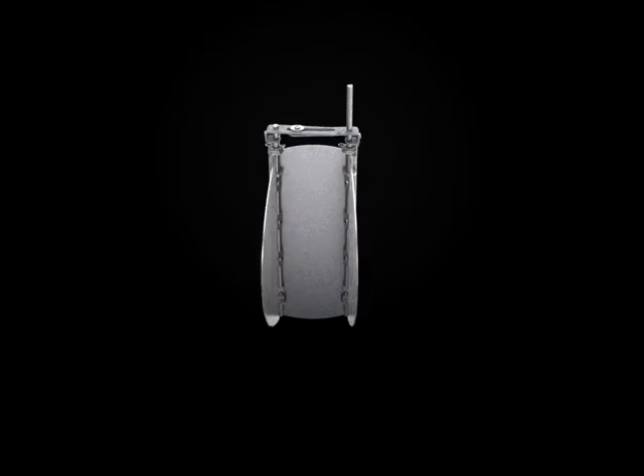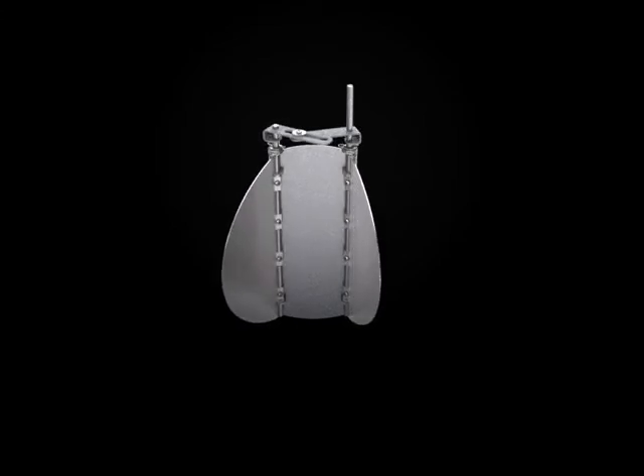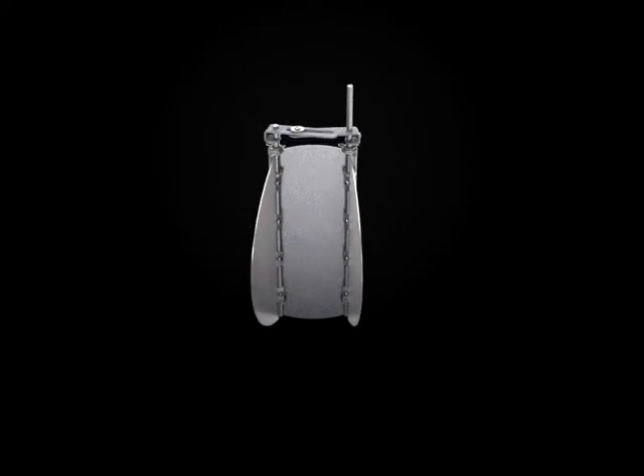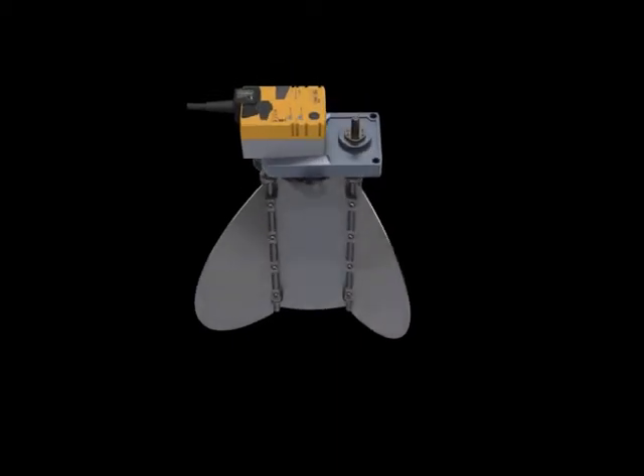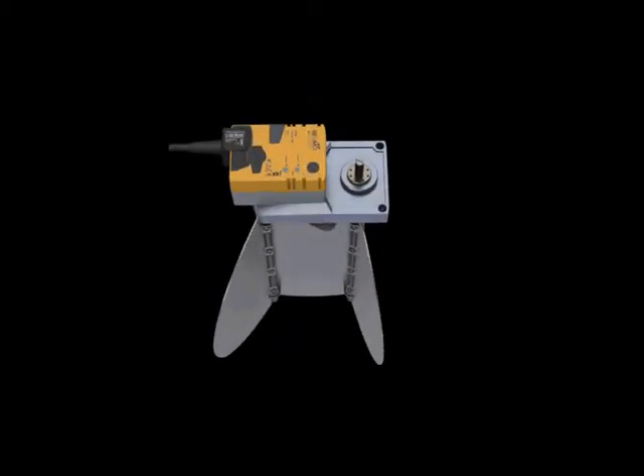Turndowns of up to 10 to 1 while maintaining accuracies of 5% of reading over the flow range ensure precise airflow control for the AccuValve. The high-speed electric actuator delivers superior speed of response.